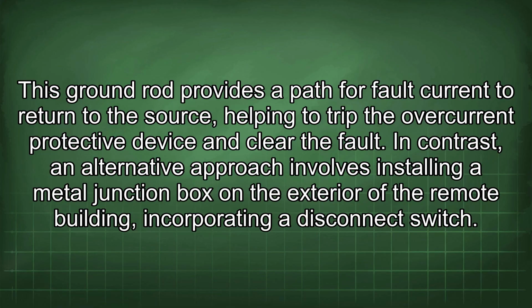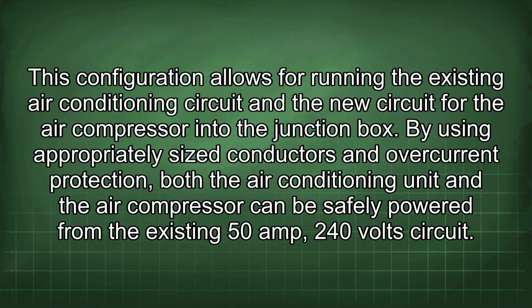In contrast, an alternative approach involves installing a metal junction box on the exterior of the remote building, incorporating a disconnect switch. This configuration allows for running the existing air conditioning circuit and the new circuit for the air compressor into the junction box. By using appropriately sized conductors and overcurrent protection, both the air conditioning unit and the air compressor can be safely powered from the existing 50-amp 240-volt circuit.